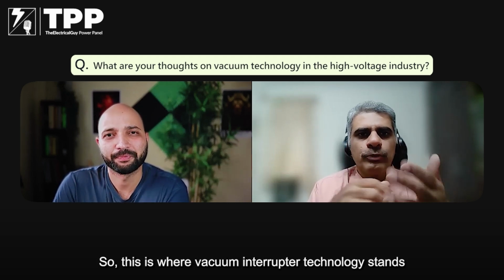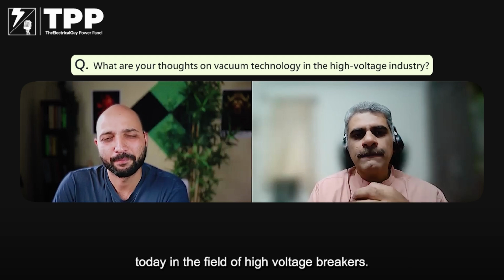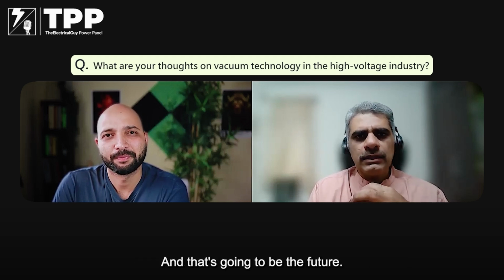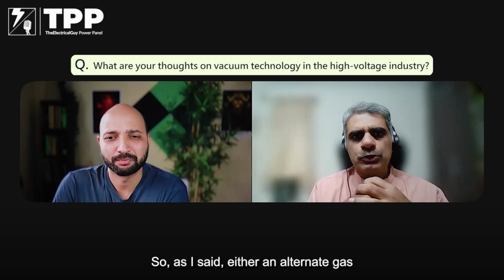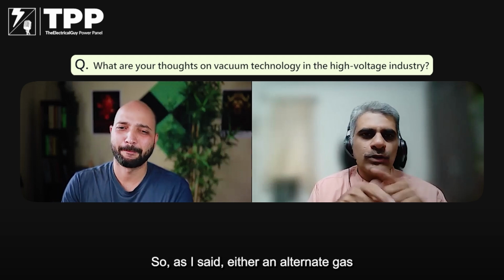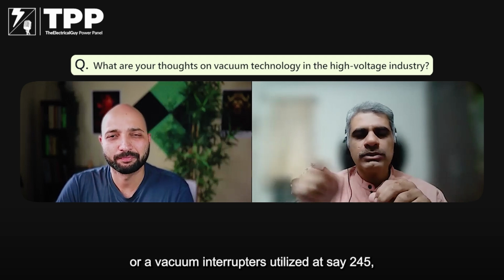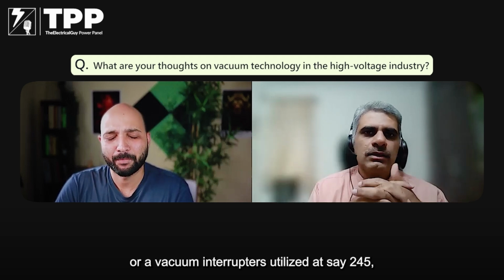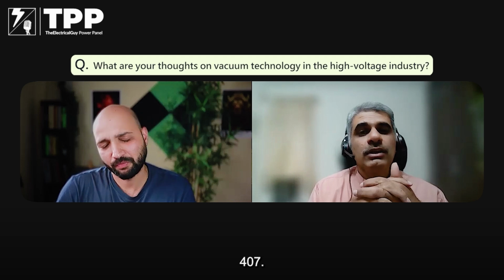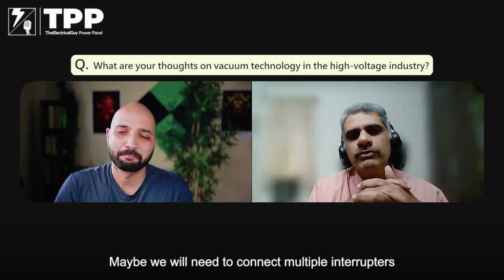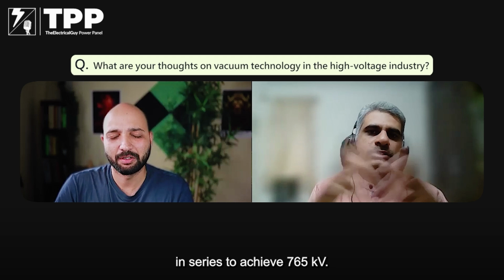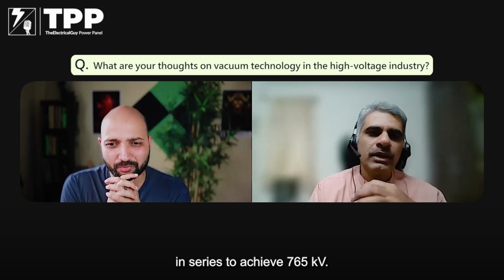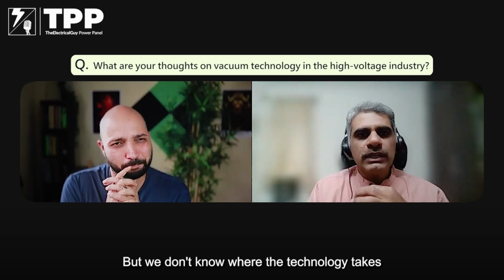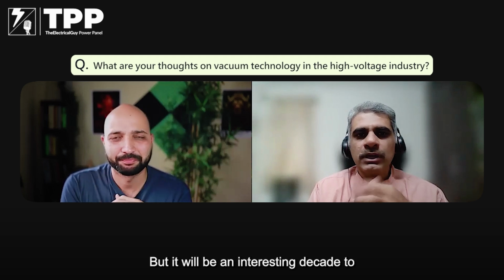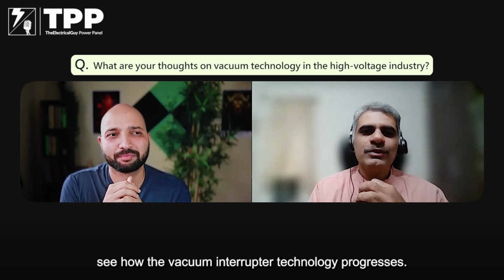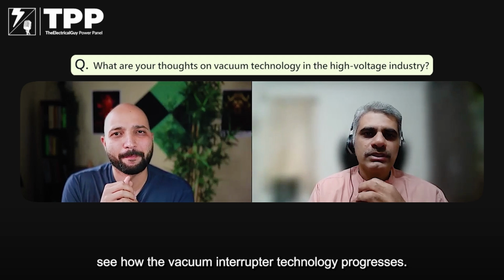So this is where vacuum interrupter technology stands today in the field of high voltage breakers, and that's going to be the future. As I said, either an alternate gas or vacuum interrupters utilized at, say, 245, 400, 765 kV looks quite difficult. Maybe we will need to connect multiple interrupters in series to achieve 765 kV. But we don't know where the technology takes us in the next decade. It will be an interesting decade to see how vacuum interrupter technology progresses.